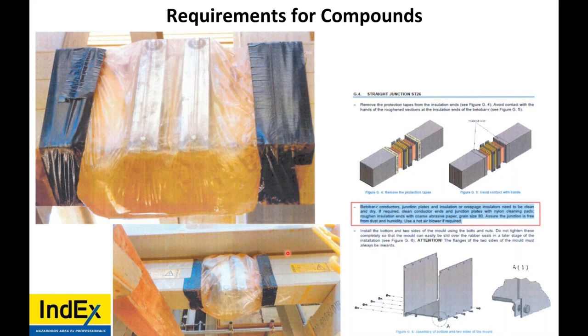Now, the problem is, what happened to the encapsulant? Did it absorb that water? Will this joint fail in the future? Design life of this project is 40 years. You think anybody will remember this problem in 40 years' time if it does fail? Probably not. Who will they blame? The installers or the manufacturers? Probably the manufacturer at that point. So the manufacturer's name is going to take a hit because nobody followed the certificate and the IOMs. Okay? Don't do like this.